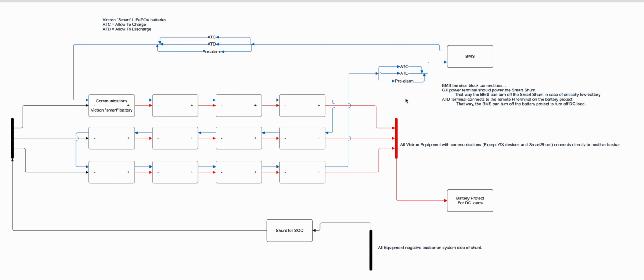Where this can fail is if the batteries get so deeply discharged that the BMS itself has to turn off, then the inverter might not be able to power up. But that's why there's a GX power port. The GX power port will supply power to your smart shunt. It'll supply power to your Cerbo. It'll supply power to all those things. And so after the ATD terminal shuts off, the BMS will keep those other communications devices live for a certain amount of time. But if the battery gets so low that it needs to even turn those off, then it'll turn those off to preserve that last little bit in the batteries so that the inverter will still be able to turn on and charge up the batteries if you start a generator or something like that.